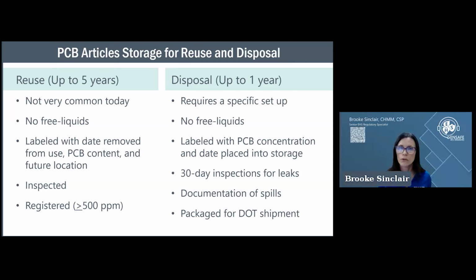You've got to do some things. You can keep it for 5 years without doing anything extra, but you have to make sure there are no free liquids—no oil leaking out of that transformer or article. It's got to be labeled with the PCB content on it. And you've got to determine the future use of this. EPA didn't want electrical equipment containing PCBs sitting around indefinitely—if it doesn't have a use, it needs to move for disposal. There are inspection requirements too, and any PCB transformer at 500 parts per million or greater has to be registered with EPA. You've got 30 days to do that, so keep that in mind.